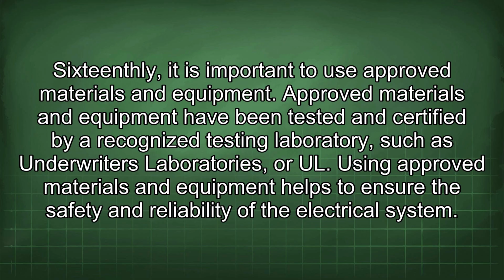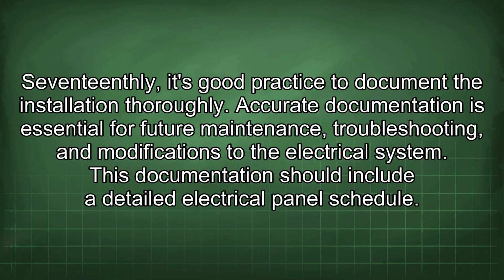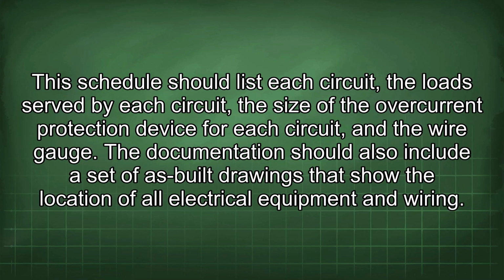Using approved materials and equipment helps to ensure the safety and reliability of the electrical system. 17thly, it's good practice to document the installation thoroughly. Accurate documentation is essential for future maintenance, troubleshooting, and modifications to the electrical system. This documentation should include a detailed electrical panel schedule. This schedule should list each circuit, the loads served by each circuit, the size of the overcurrent protection device for each circuit, and the wire gauge.